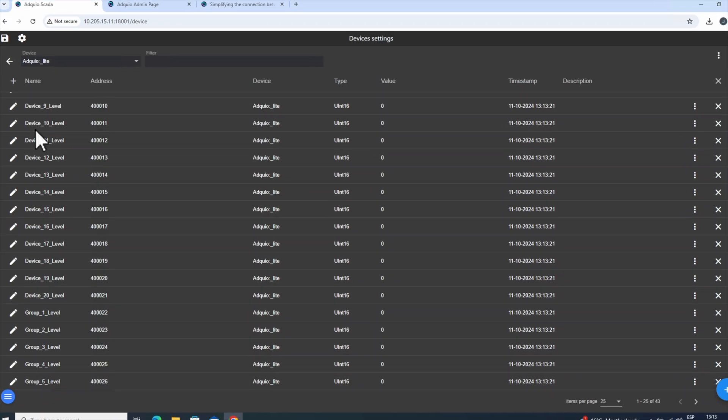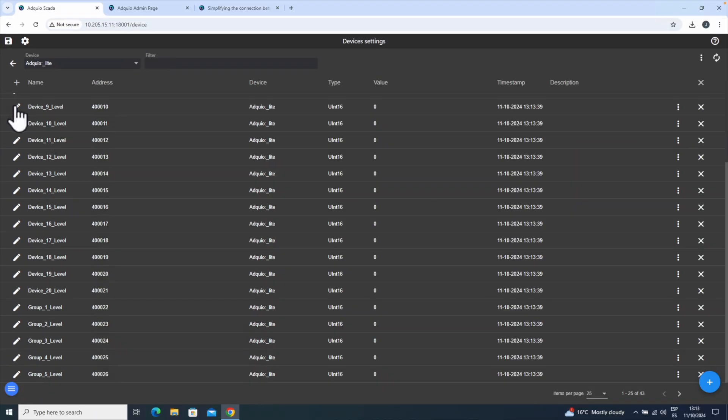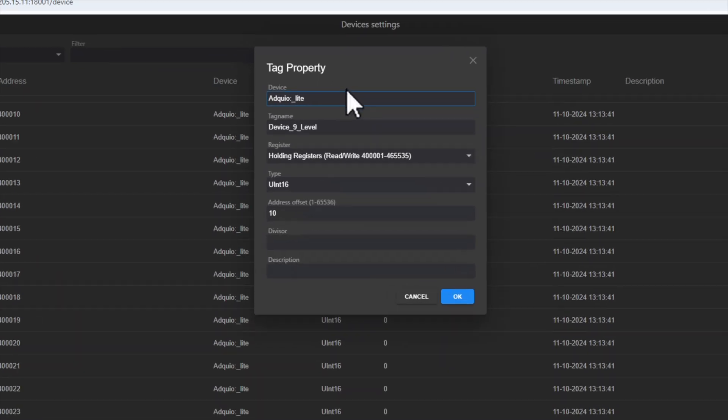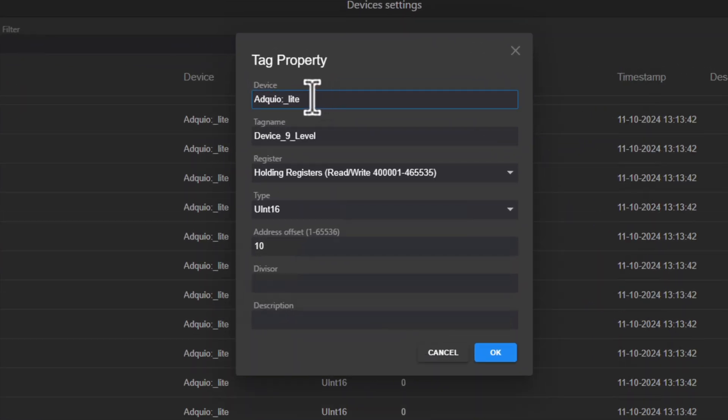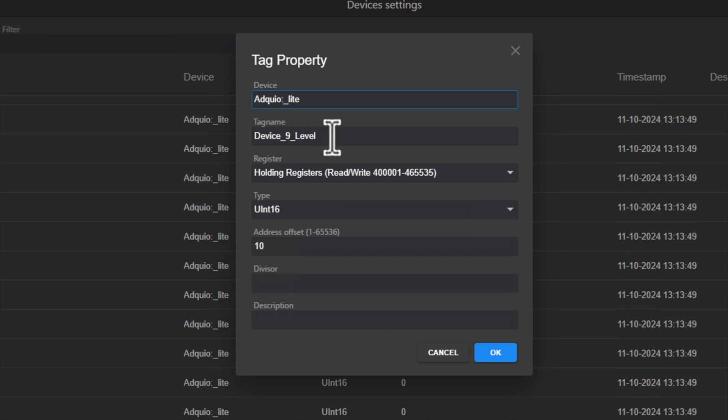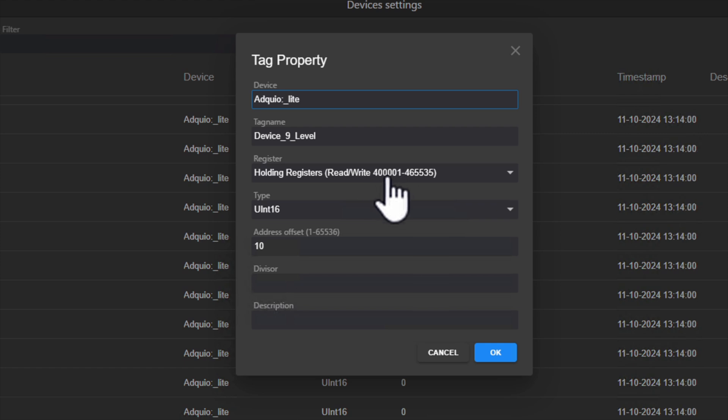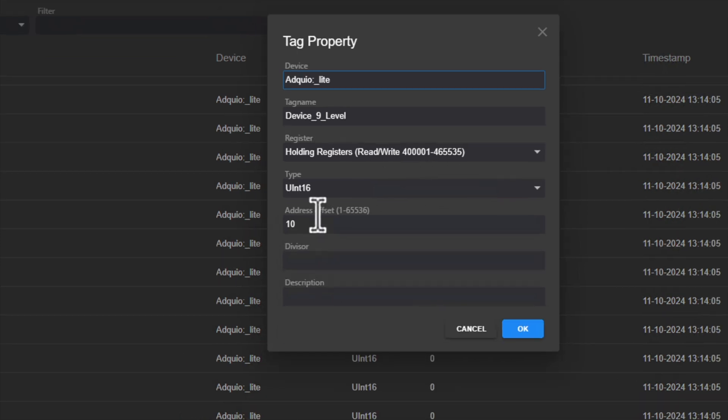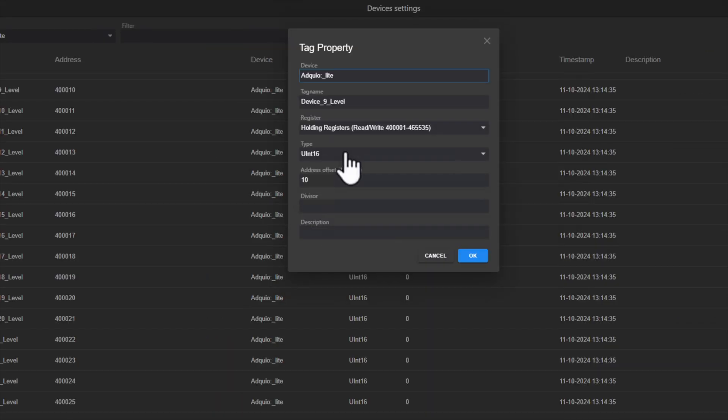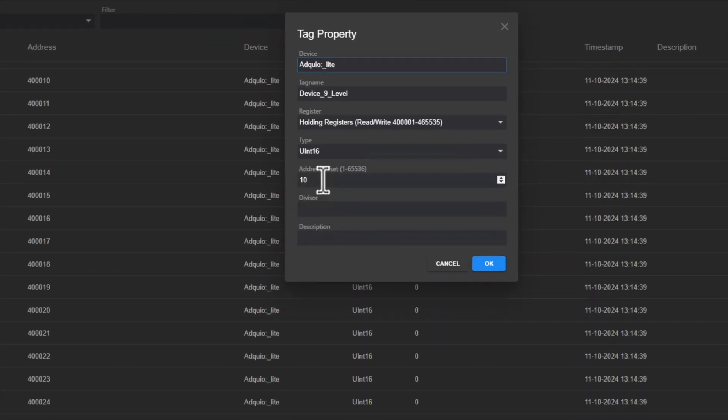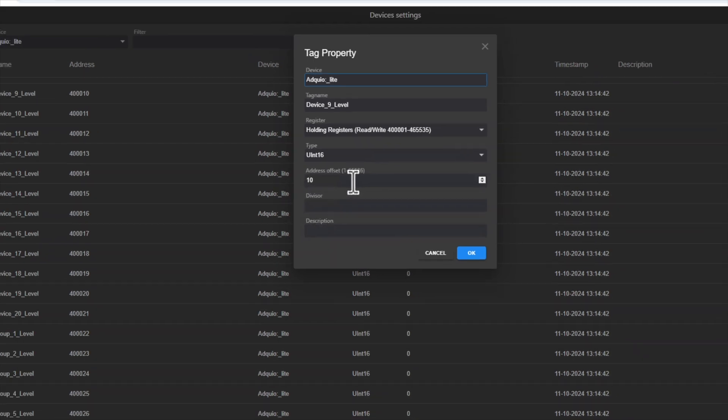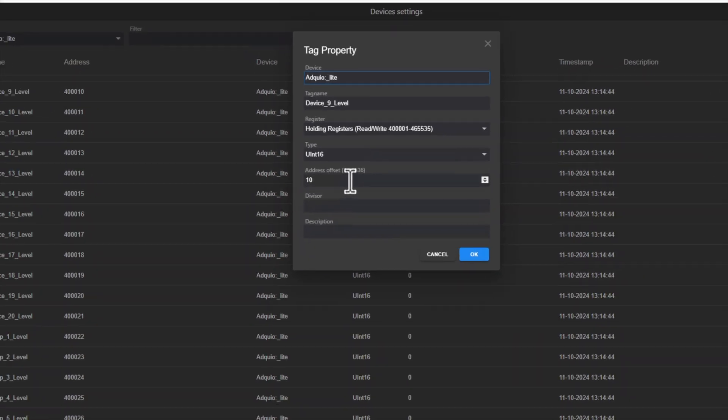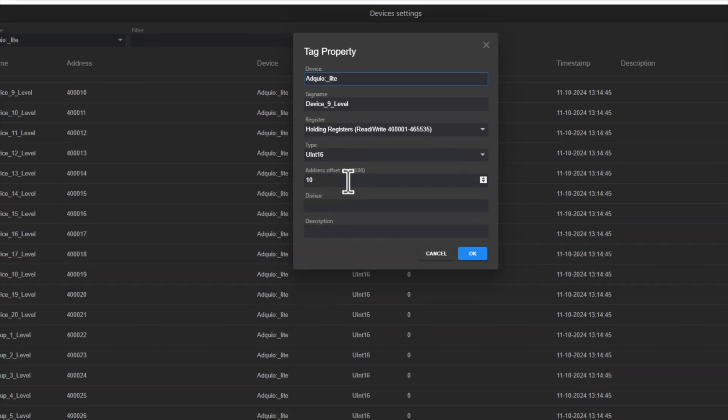Additionally, we have all the variables with the names they had in Adquio coming from Adquio Lite, with their correct addresses configured. Let's open one of them to take a look. It comes from Adquio Lite. It's the Device 9 level. It's a holding register. And because it's a holding register, SCADA automatically adds it to the address, 400,000. You'll notice that although the address is 10, if you compare these addresses with those from Adquio, within SCADA it's always one higher, because Adquio starts counting from 0 and SCADA starts from 1, so it always moves forward by 1.